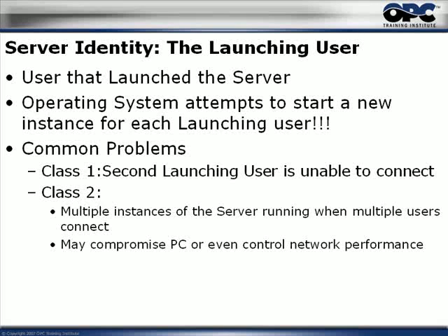With those single-instance servers, the first user is able to connect but the second user is not, because the operating system tries to start a new instance and the OPC server says it already has one running and refuses to start another. The second person will be refused. As soon as the first person terminates their connection, the second person can get in — but if the first person reconnects, they'll be refused because the second person now holds the connection.